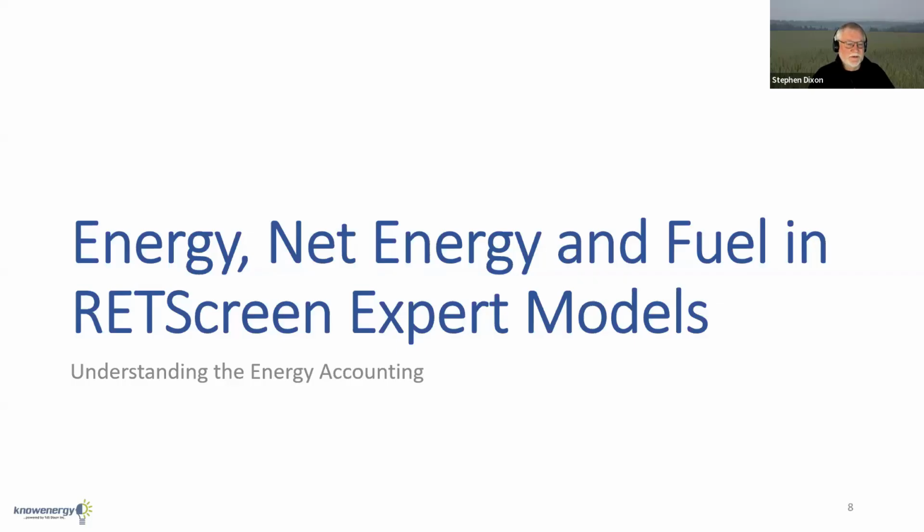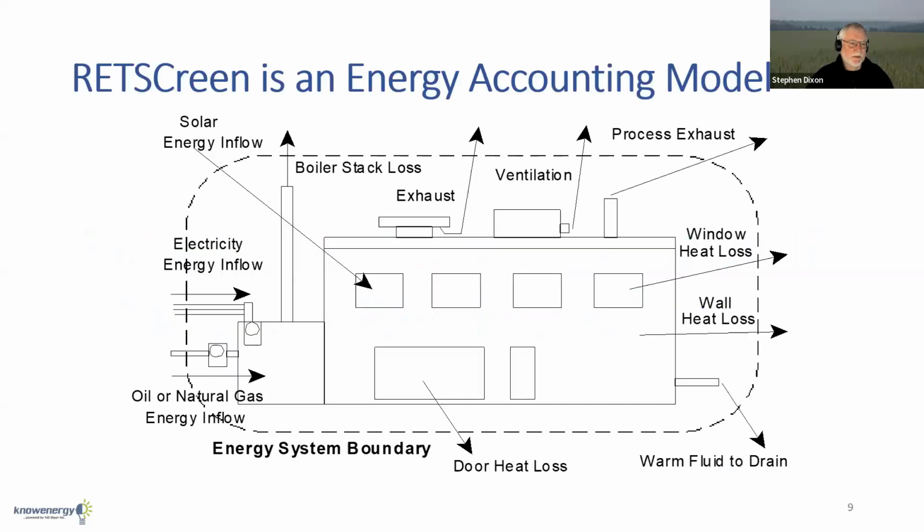Now, I'm going to introduce some terms. I'm going to introduce the terms energy and fuel. And if you've used RETScreen before, you'll see that. But if you haven't seen it before, we'll cover that off very quickly here. But then I'm going to introduce the term net energy. And what I'm talking about here is how RETScreen allows us to take into account the internal heat gains, lighting, computers, solar gains, all those kinds of things that contribute to displacing heating fuel in a building or increasing cooling load in a building. So we're going to sort of dissect this one a little bit.